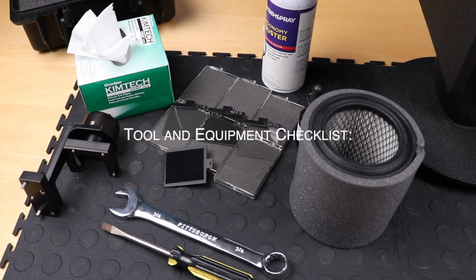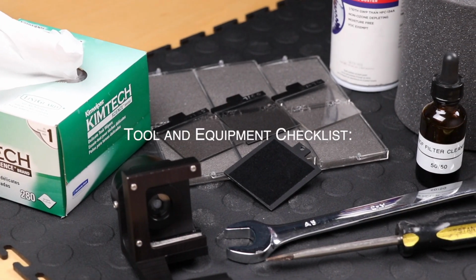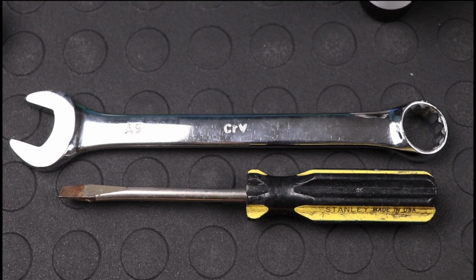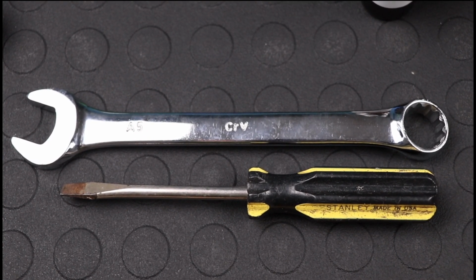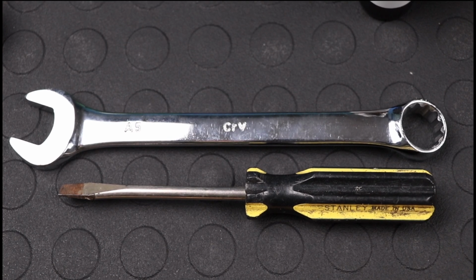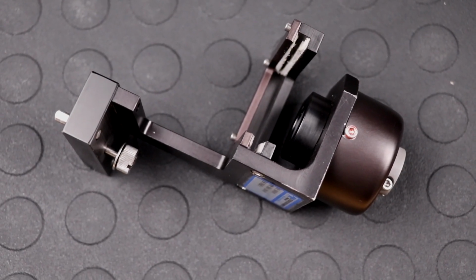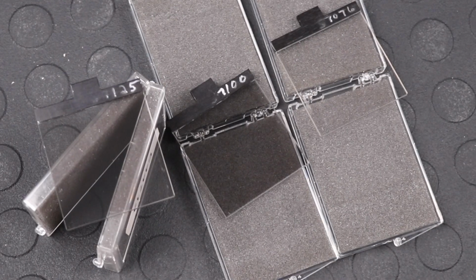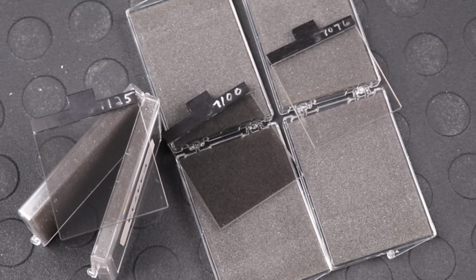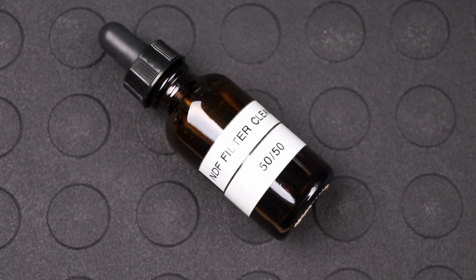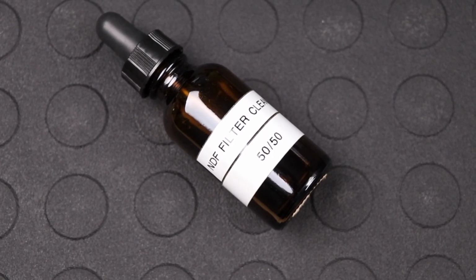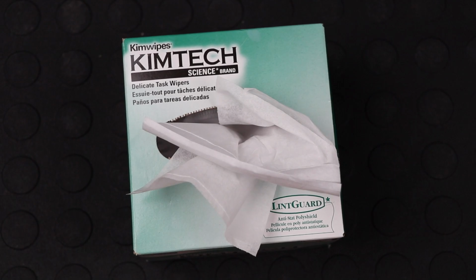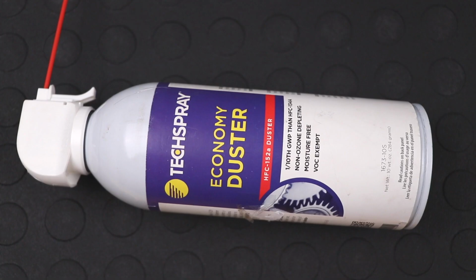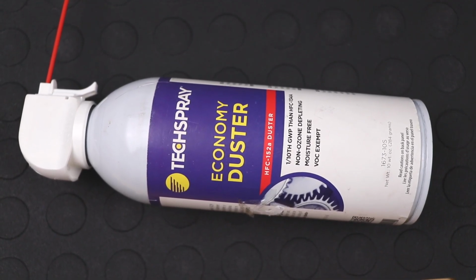So let's begin routine maintenance and perform a cleaning and on-stack calibration. First, let's review our tool and equipment checklist. We will need a standard screwdriver, a 3/4 open-ended or adjustable wrench, calibration fixture, neutral density filters, cleaning solution of 50% DI water and 50% alcohol, lint-free cloth, canned air, and a blower filter.